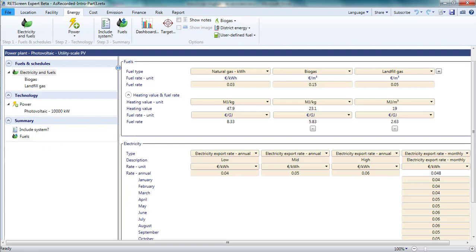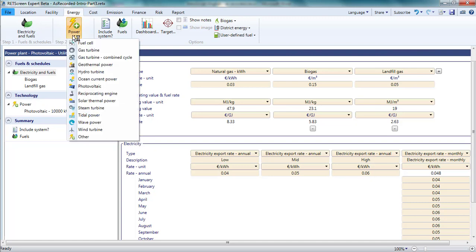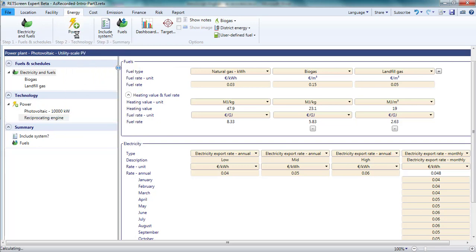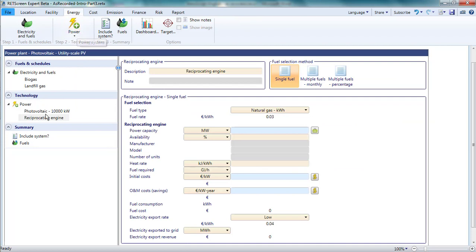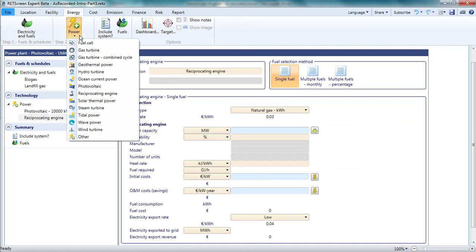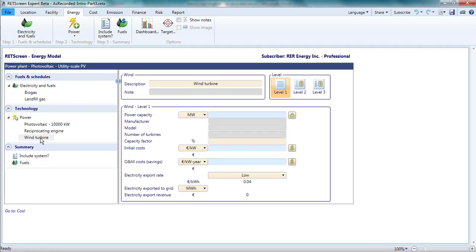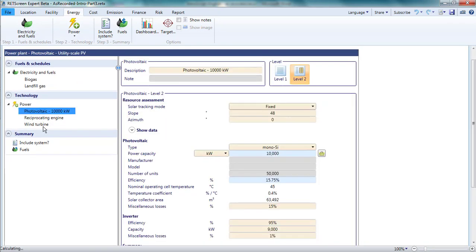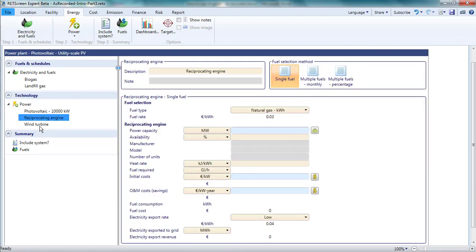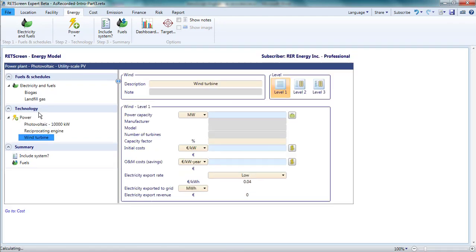When I am satisfied with the electricity tariffs and fuels available to work with in my project, I proceed to the technology elements. Note that while I can access this from the navigation pane on the left or from the menu bar, the result is very different. From the menu bar, picking a technology from the drop-down list adds a new technology. I could add a reciprocating engine and wind power to my existing photovoltaic project in this way, for example. From the navigation pane, in contrast, clicking on a row selects from among previously added technologies.